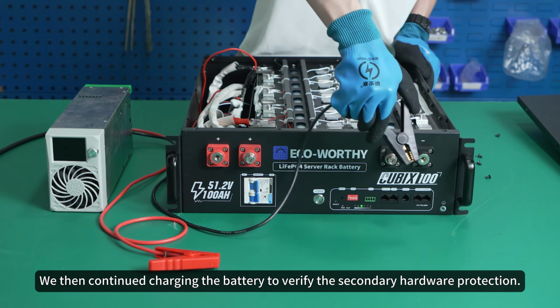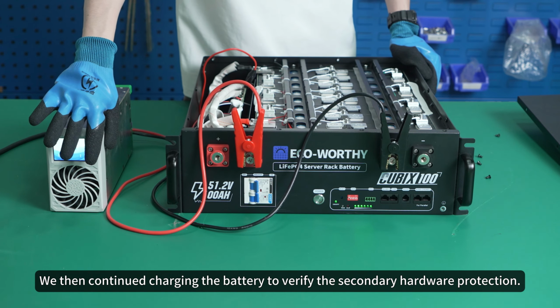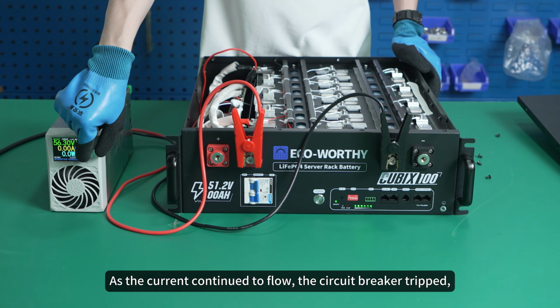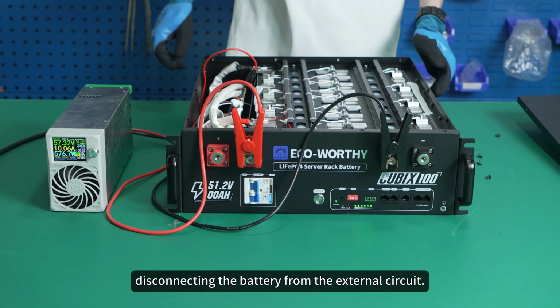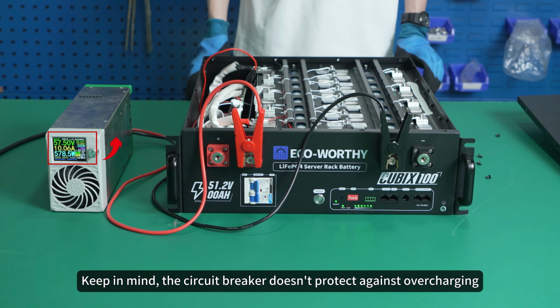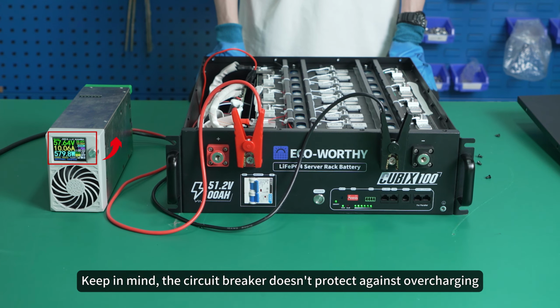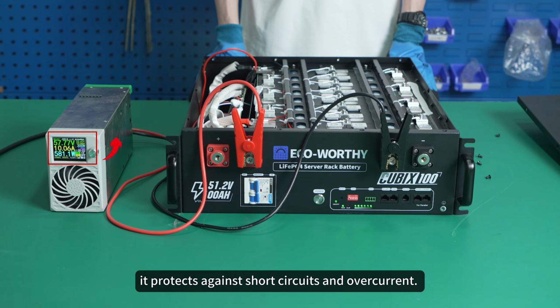We then continued charging the battery to verify the secondary hardware protection. As the current continued to flow, the circuit breaker tripped, disconnecting the battery from the external circuit. Keep in mind, the circuit breaker doesn't protect against overcharging, it protects against short circuits and overcurrent.